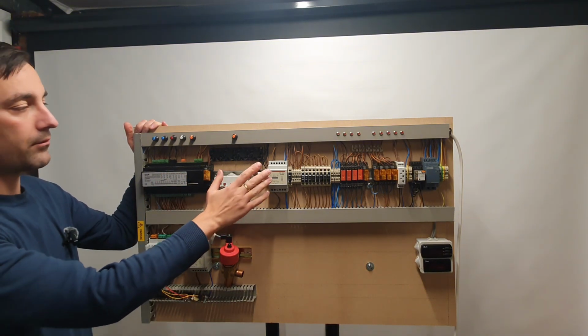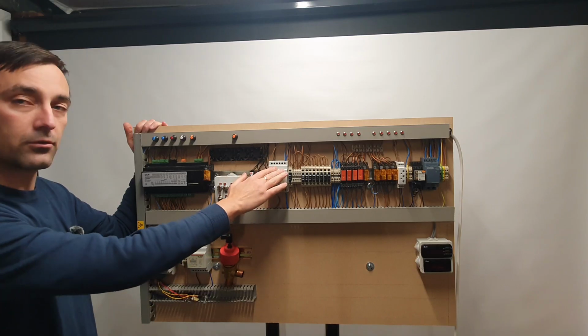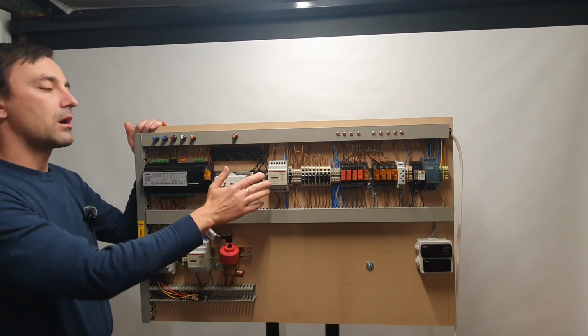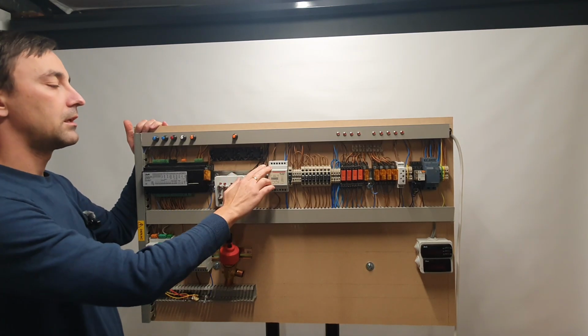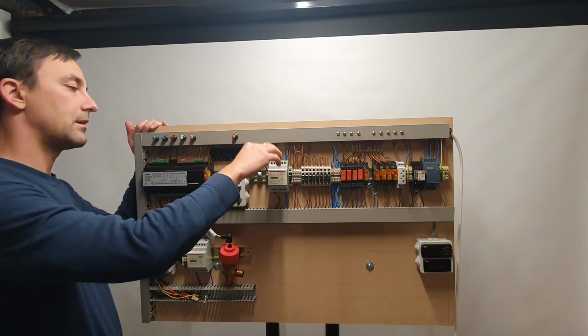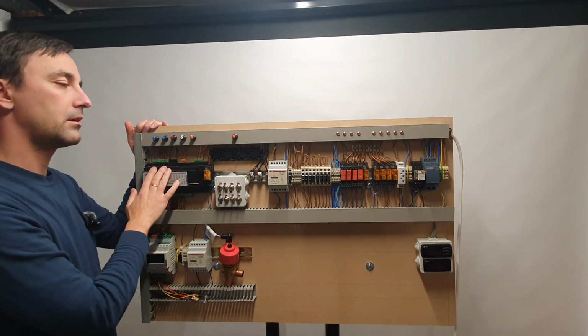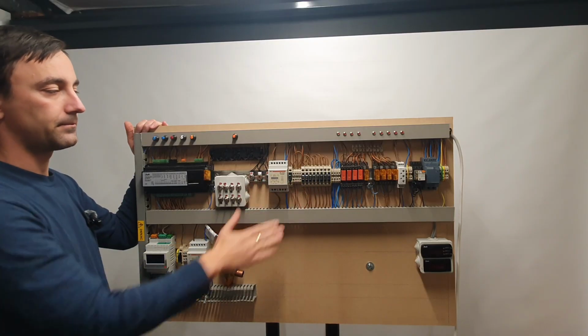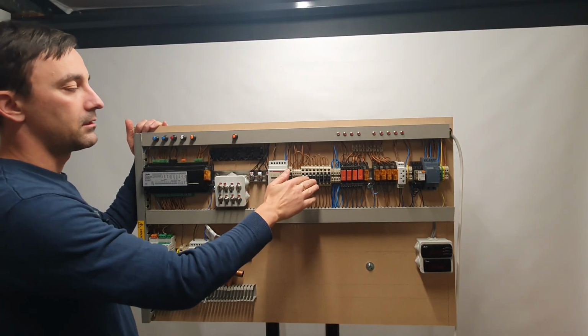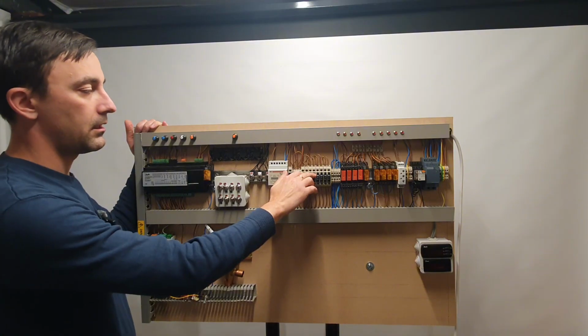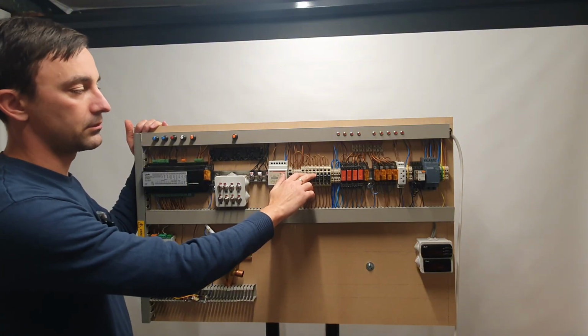Next, we have a 24 volt transformer. The reason why I had to use one is because the safety circuit for our compressor and the feedback to the controller is on 24 volts. So each safety circuit is protected by its own fuse.